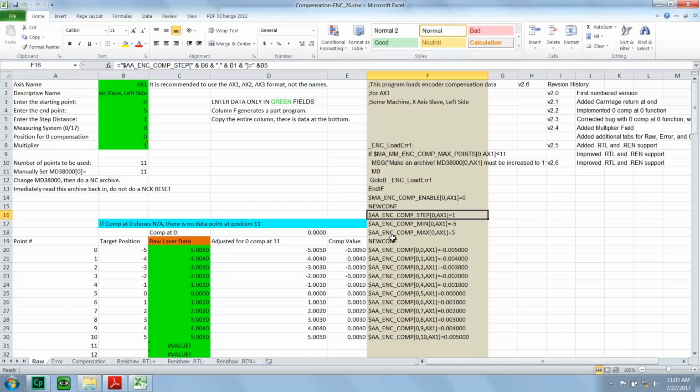So, for example, if we calibrated the machine in January, everything was good, we've got a good comp file, we've got that saved. We recalibrate in March because that's our schedule, everything's good, everything's fine. We recalibrate in May, everything's fine. But then we find out that we'd somehow started making bad parts in April. What happened? We look in the comp files and we compare the March file versus the May file, and we see that all of a sudden there were some grossly different numbers. If you had kept these files, you'd be able to do that. It's a choice, not necessary. It depends on what your shop decides to do.